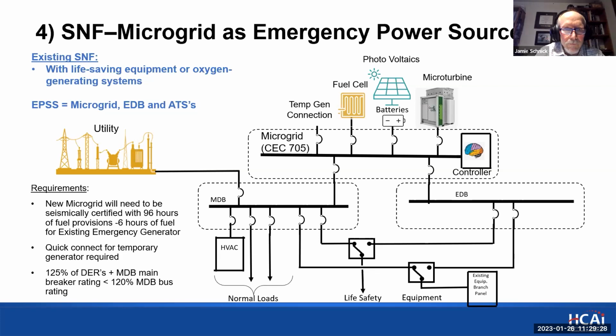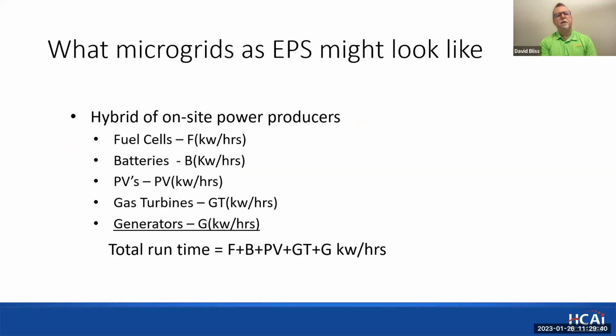That's an aggregate. The intent is that the facility can operate for the 96 hours. So in more concrete terms, if you had batteries, a fuel cell, and a generator, the total sum of all those assets put together would have to supply 96 hours of continuous power up to the level required for the health and safety systems.